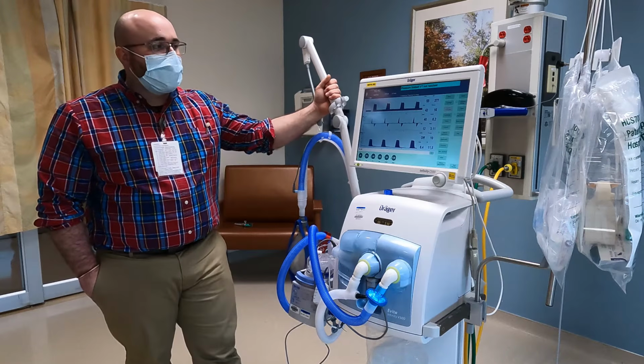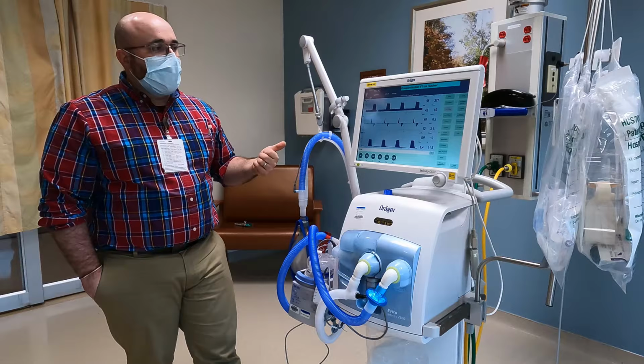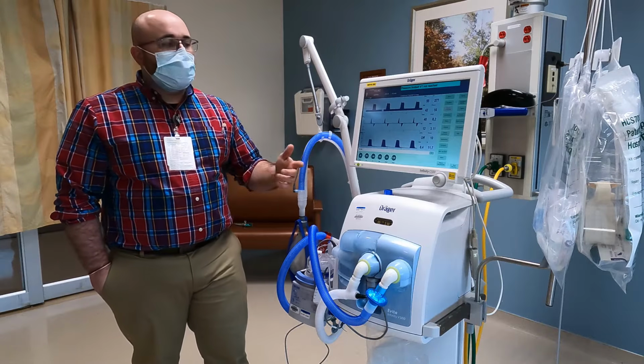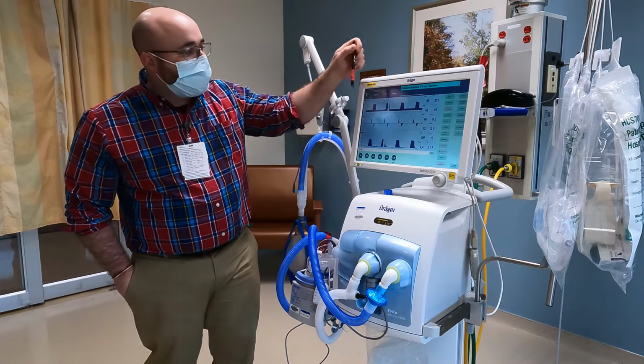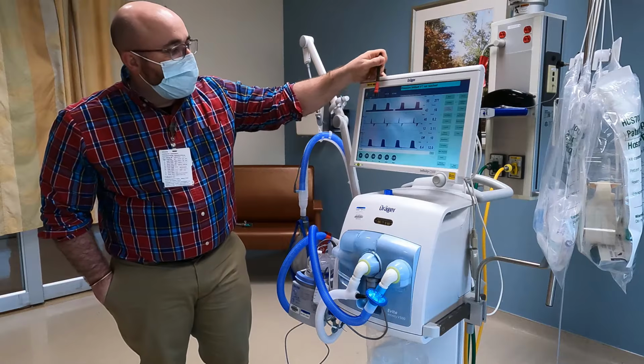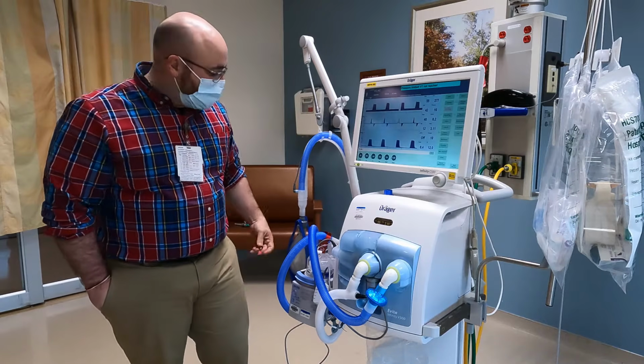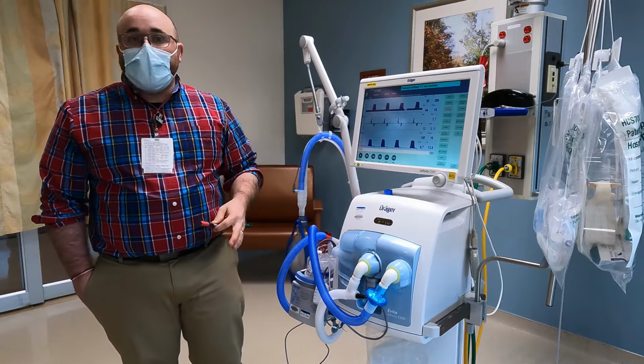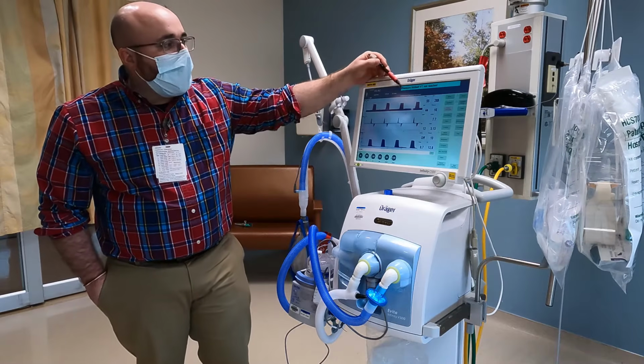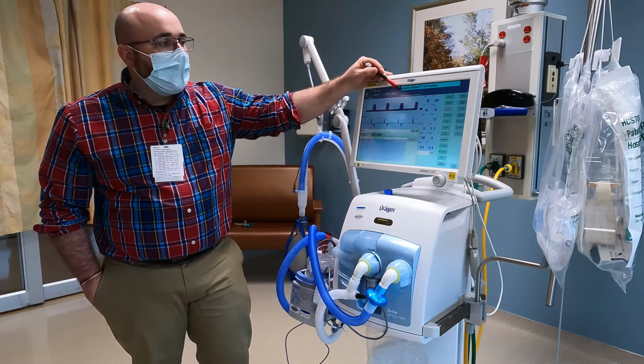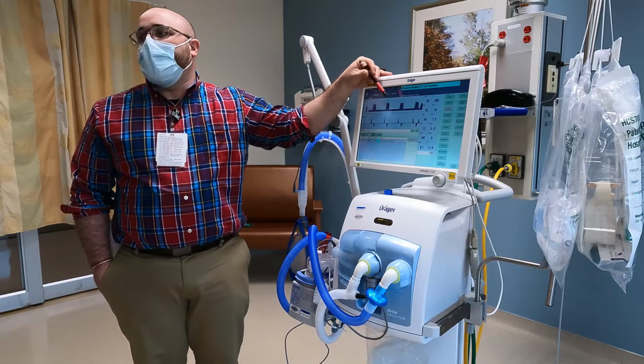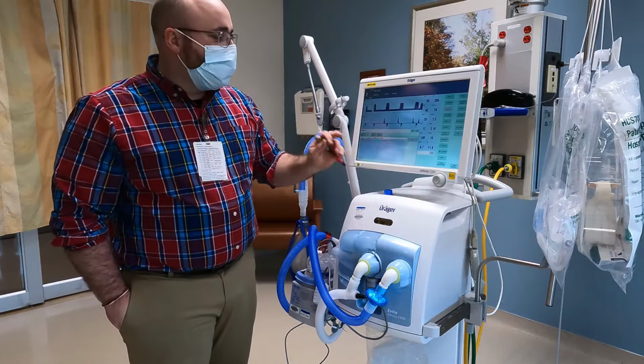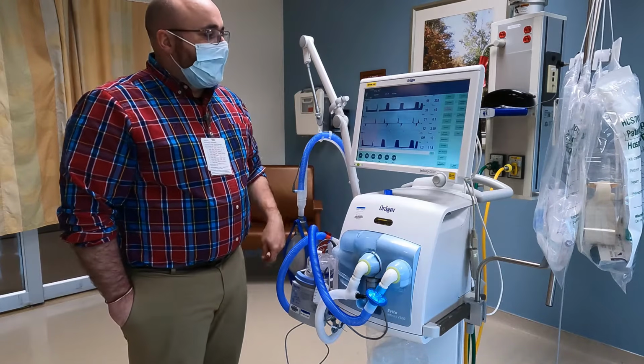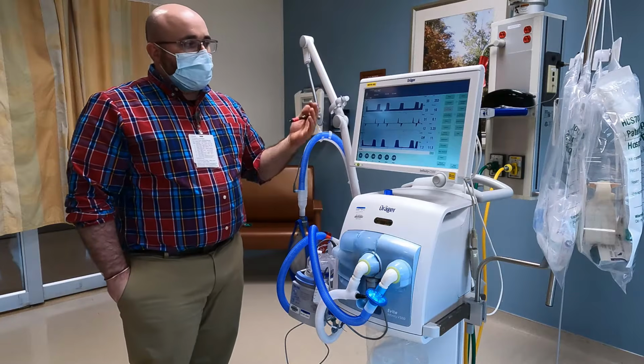That's real bad, because how do we ventilate? We have to get the air out. I don't care what you give it in. And the reason we're not getting it out is because we're limiting each breath with the pressure. And that's just because of the test lung. Could definitely happen to your patient though. So any alarm that comes up here needs to be addressed, even if it's not like a red alarm. And it's really cool that you guys got this, because we don't see that a lot of other times.